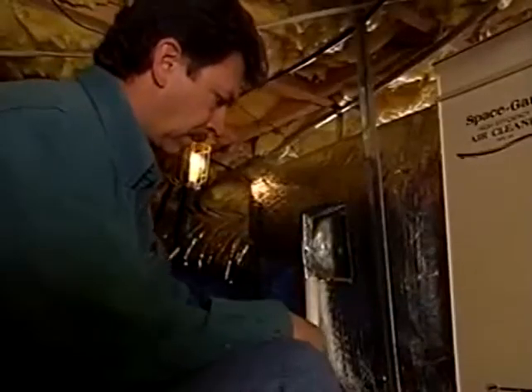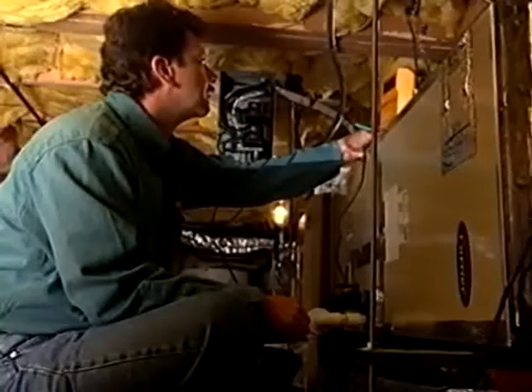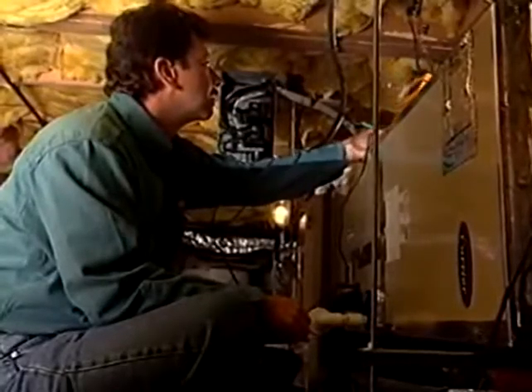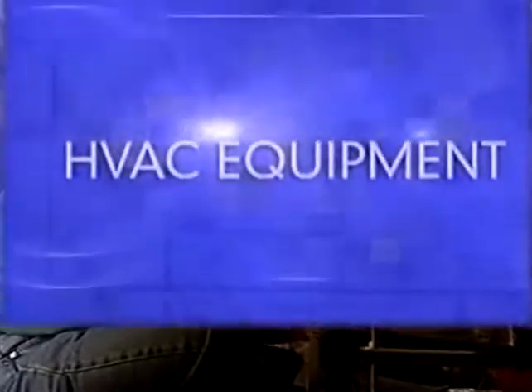Follow the same procedure on the return side, drilling a hole in the return plenum. Once you've obtained your supply and return air temperature measurements, seal the holes with UL 181 foil tape. Now you're ready to calculate the CFM to see if your unit is operating properly.